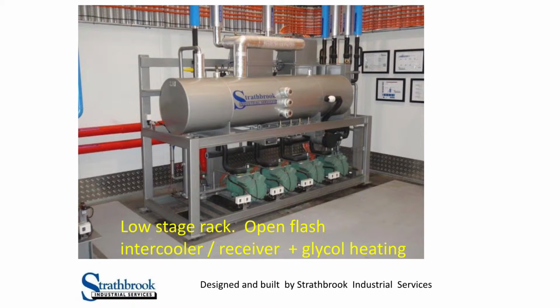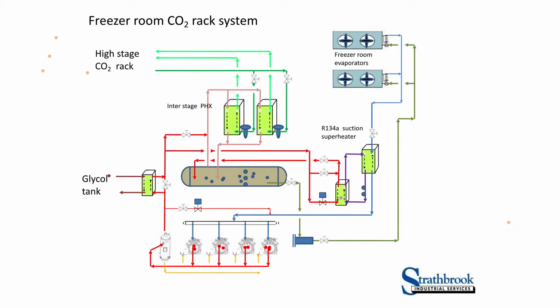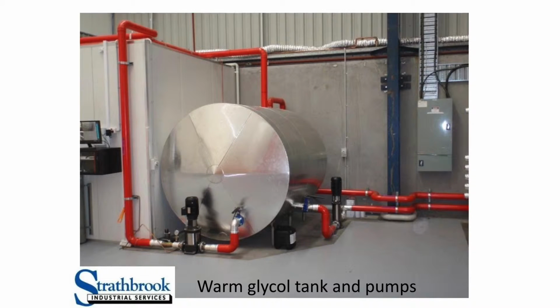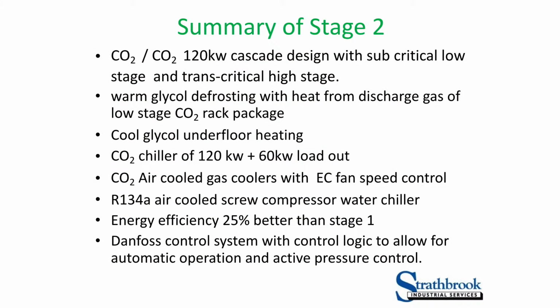There's the low temp package. In this case, we were heating the glycol off the low temperature package and not the high temperature package. That means that heat doesn't go to the high stage, so we make a 20 kilowatt saving on the high stage for the entire life of the project. So there's another flow diagram, which I won't worry about too much because we're pressed for time. Glycol tank, and then a summary of stage 2.